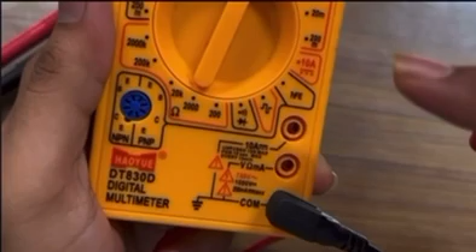Otherwise, if measuring currents less than 500 milliamps, place your red probe here. If measuring current more than 500 milliamps, place your probe over here. Be very careful with this, because if you place the probe in the wrong port and measure current more than 500 milliamps, your meter will be damaged.